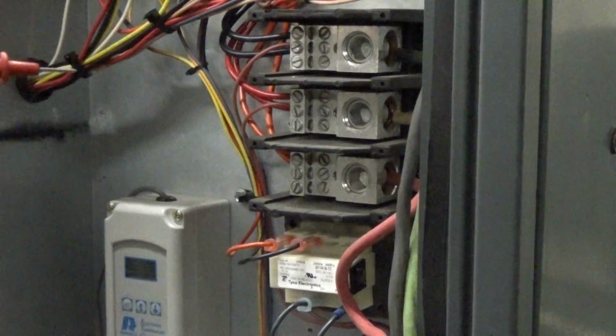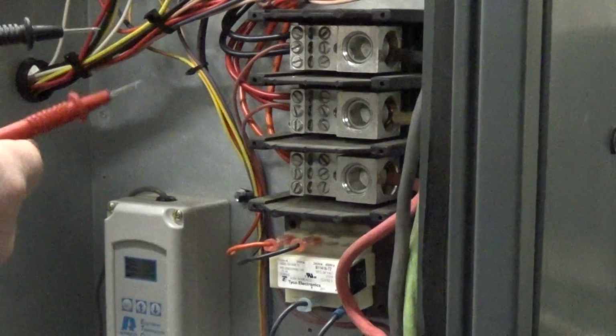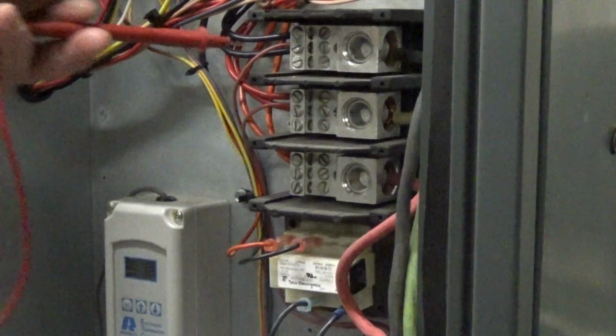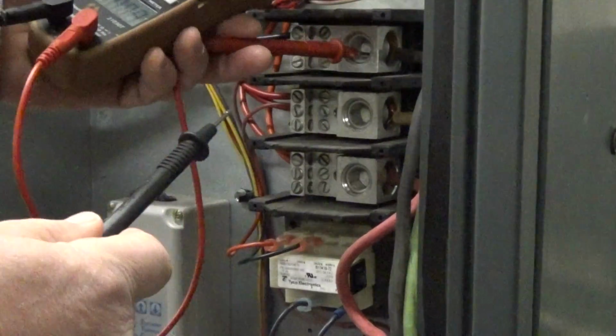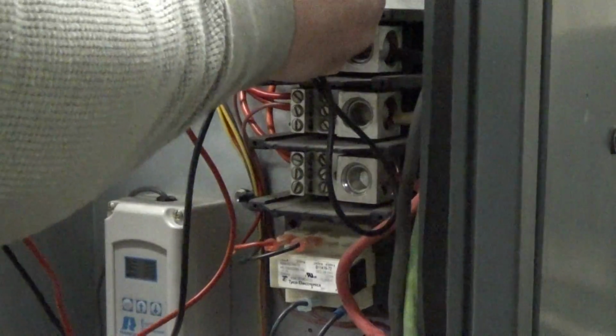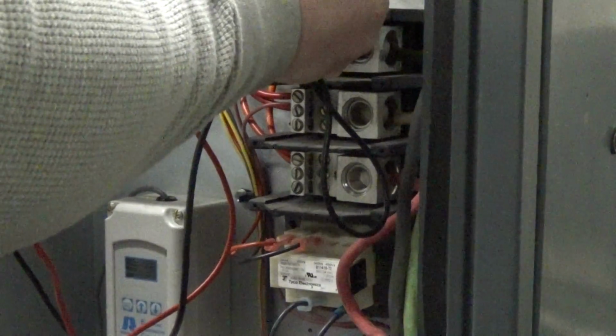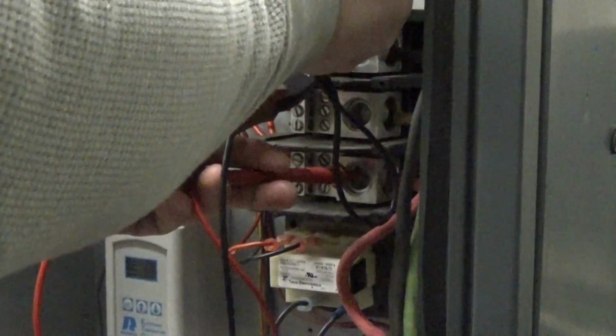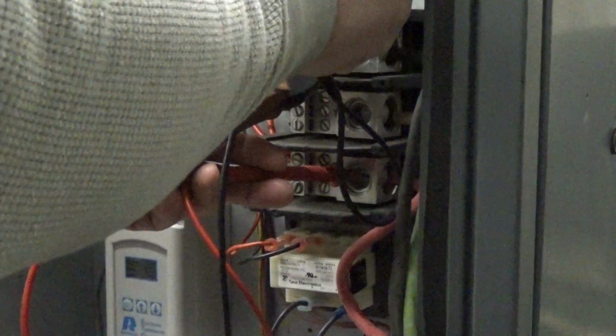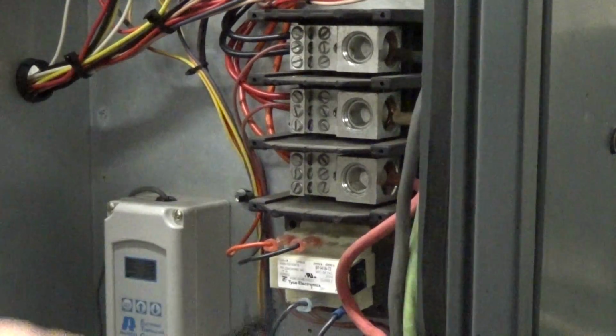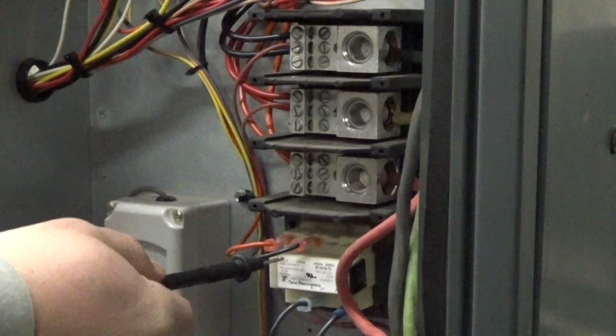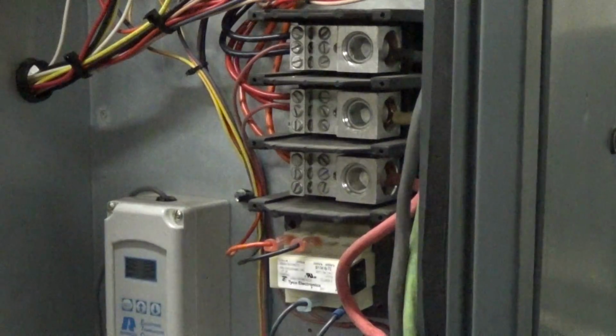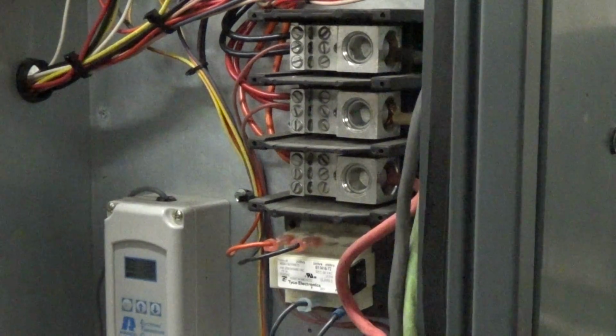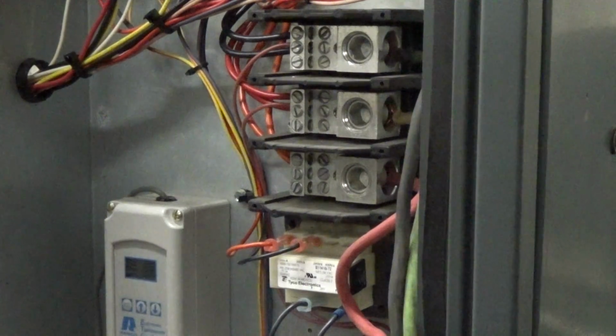In addition to that, each one of these legs to ground should measure 115. There's my ground wire there. 117. 117. 117. Okay? So again, a 3-wire connection, 3 hots, and a ground, making it a 4-wire connection. You do not need a neutral for this type of 3-phase power.